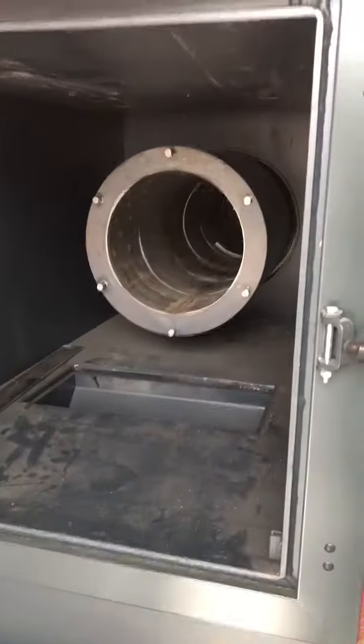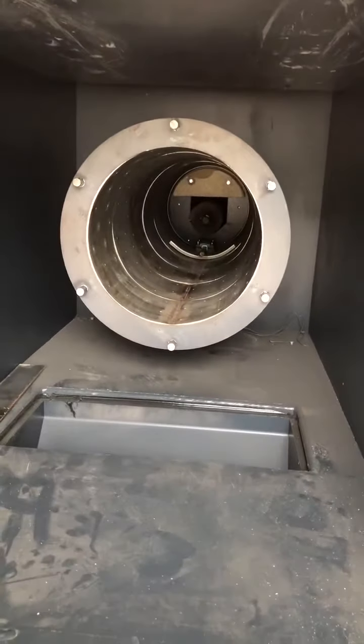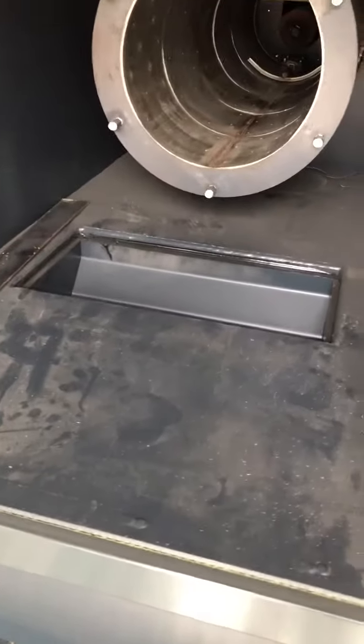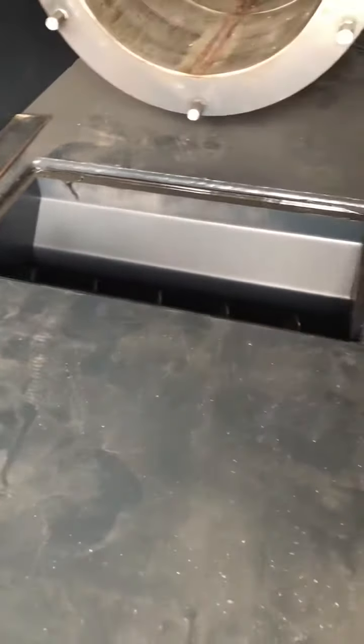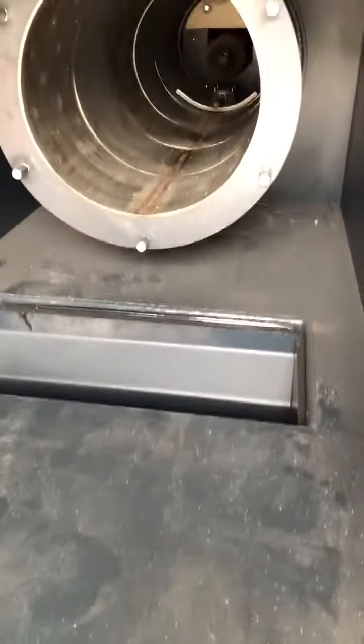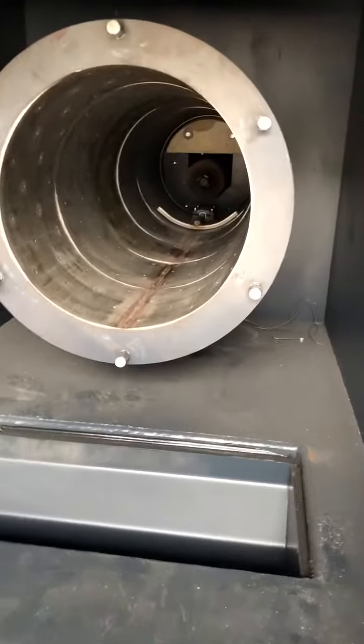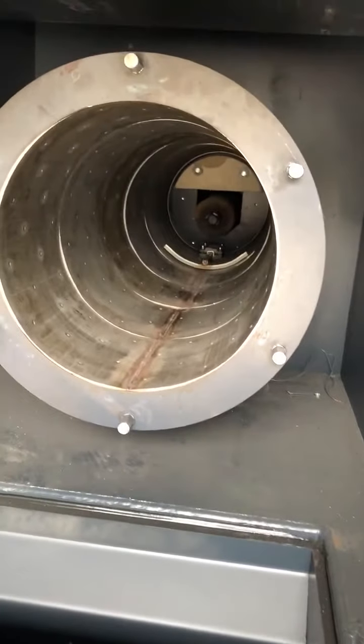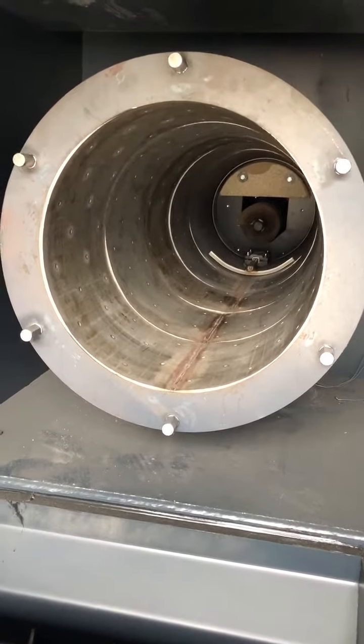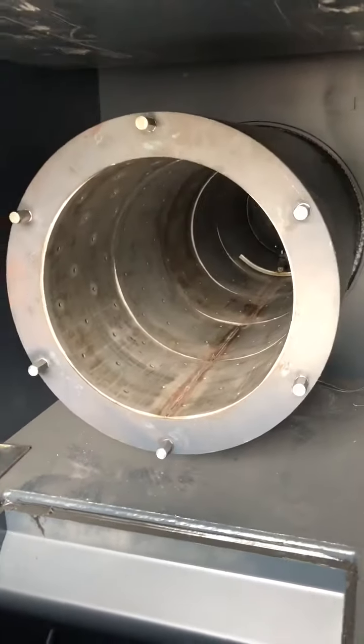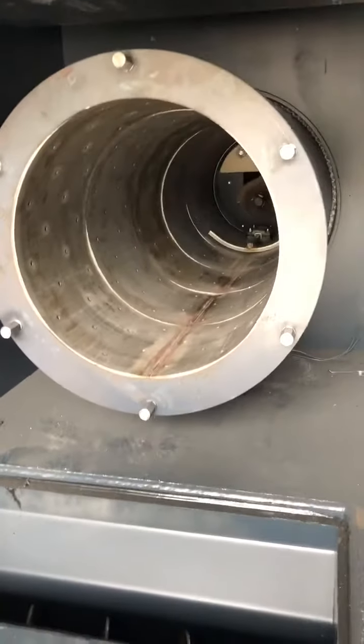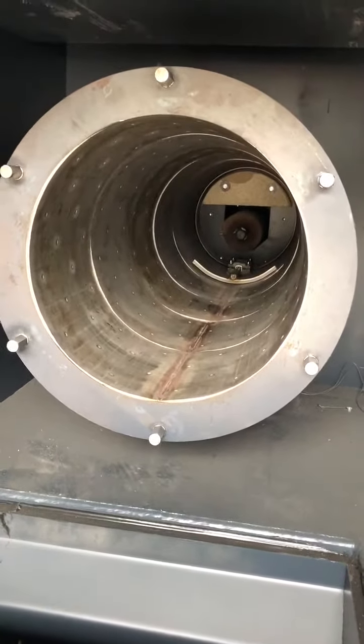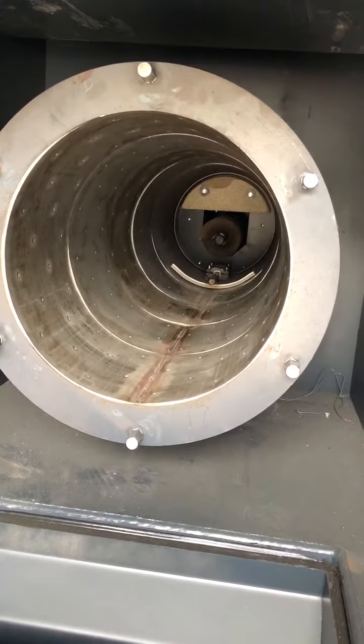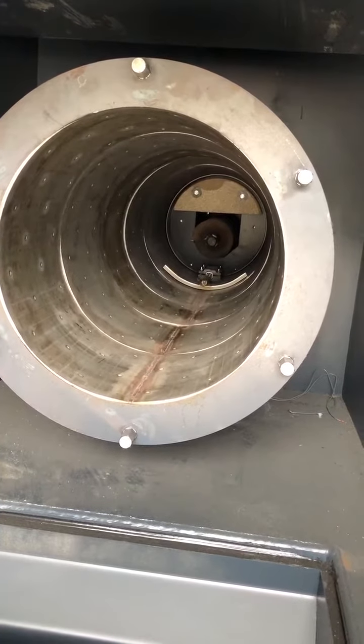In here we see the burner tube. In the bottom of the boiler here, there is the ash auger channel where the ash auger is going out to the one on the other side. In the burner tube, this is a CS150, and it's the same on the CS250. We've got 4 rings with holes in, and 1 ring in the back with no air holes in. That's a preheating zone. In the middle you can see the auger coming out, and in the bottom in the middle the ash scraper.